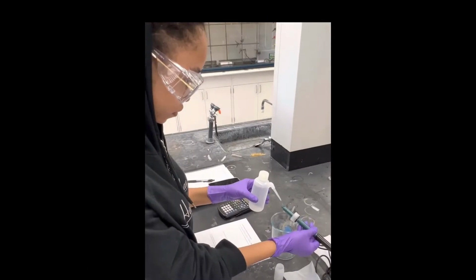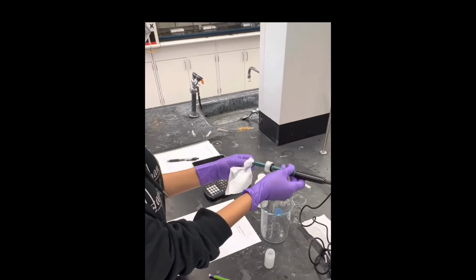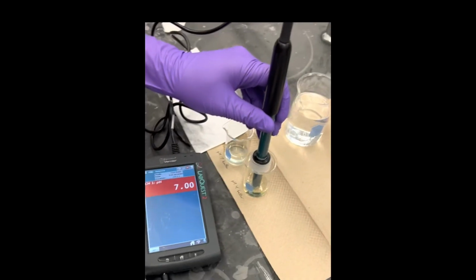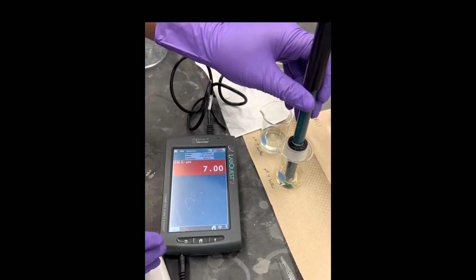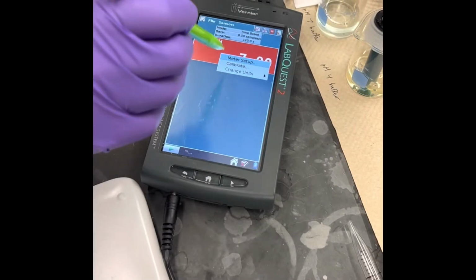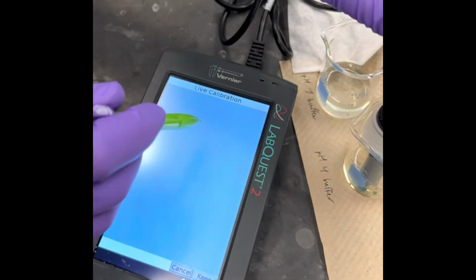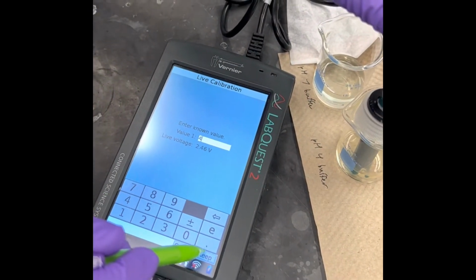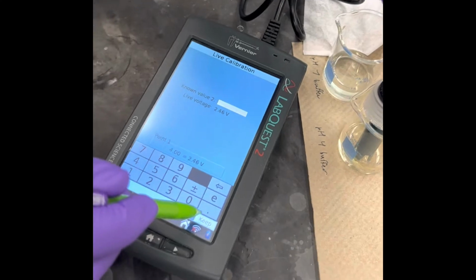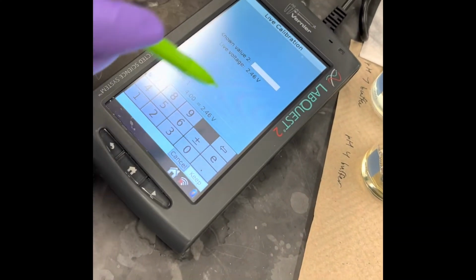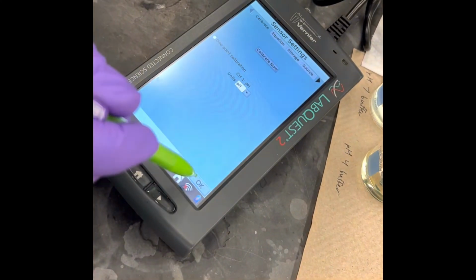Here we are repeating the same procedure and cleaning the pH probe. We are now taking the pH of our buffer 4 solution. Once again, we first have to calibrate the pH meter before we can get an accurate pH of our buffer 4 solution. After the pH meter is done being calibrated, it is now ready to take the pH of our buffer 4 solution.